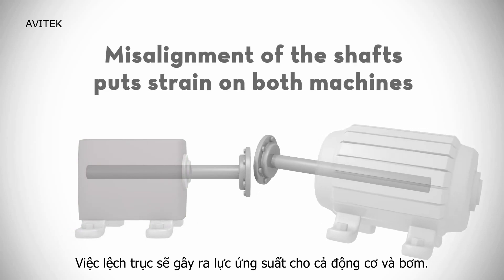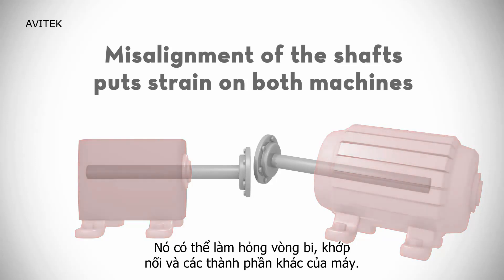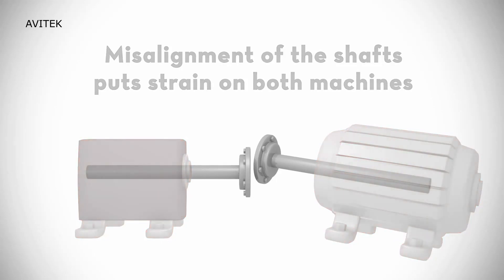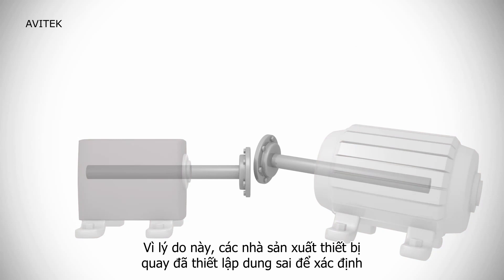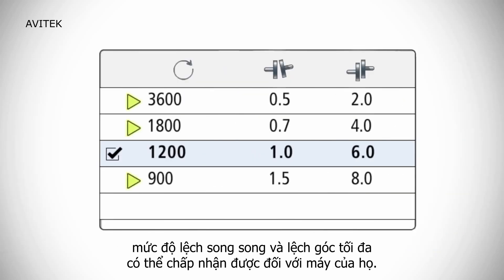Misalignment of the shafts puts strain on both the motor and the pump. It can damage the bearings, the couplings, and other machine components. For this reason, manufacturers of rotating equipment have established tolerances defining the maximum acceptable levels of angular and offset misalignment for their machines.